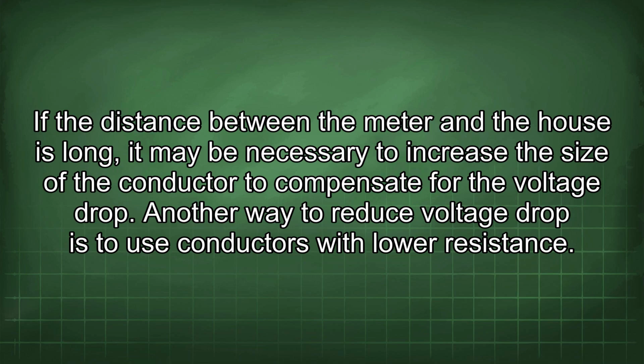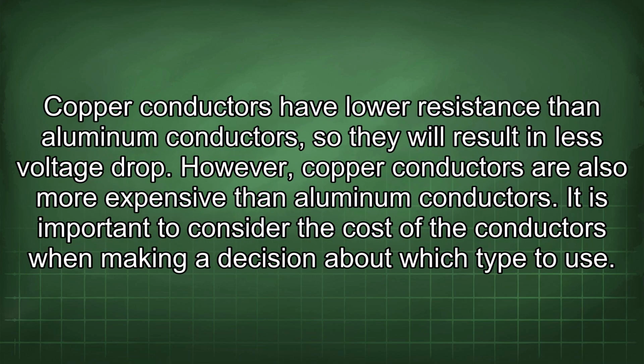Another way to reduce voltage drop is to use conductors with lower resistance. Copper conductors have lower resistance than aluminum conductors, so they will result in less voltage drop. However, copper conductors are also more expensive than aluminum conductors. It is important to consider the cost of the conductors when making a decision about which type to use.